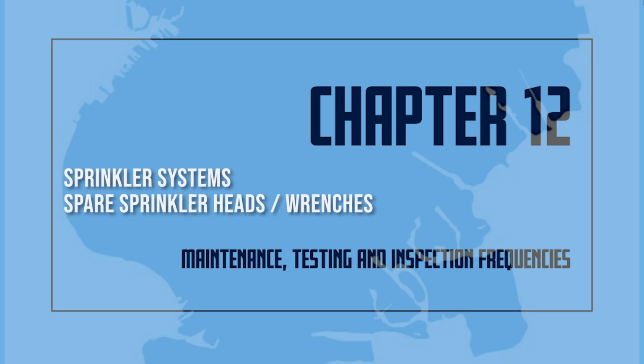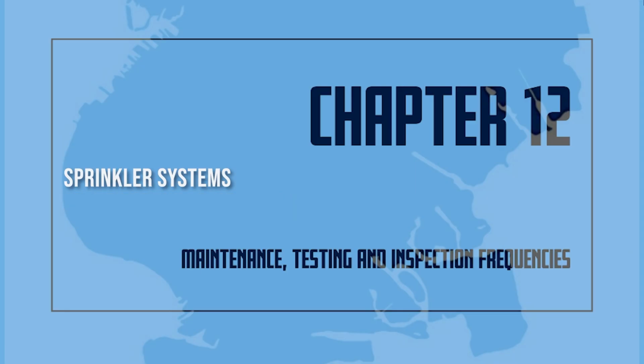Spare sprinkler heads/wrenches. The supply shall be inspected annually for the proper number and type of sprinklers and a sprinkler wrench for each type of sprinkler. Sprinklers. Sprinklers shall be inspected from the floor level annually for signs of leakage, corrosion, foreign materials, paint, and physical damage, and shall be installed in the proper orientation, such as upright, pendant, or sidewall.